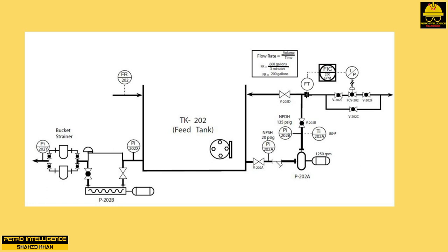Note that if pump is multistage, be sure that the minimum flow system is lined up. In some cases, the pump may be started to press up or take the slack out of the line. 7. Recheck pump's lineup and start pump.